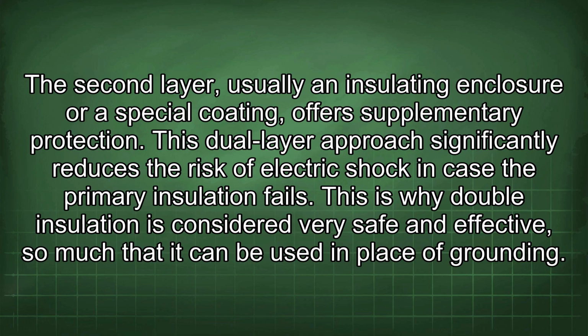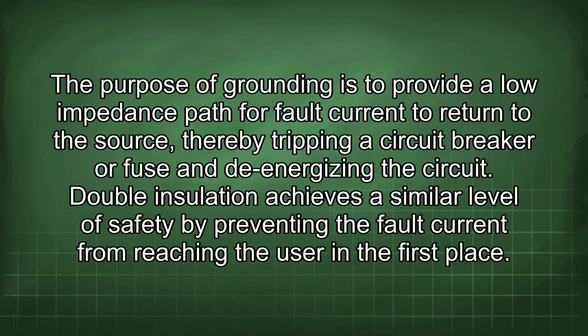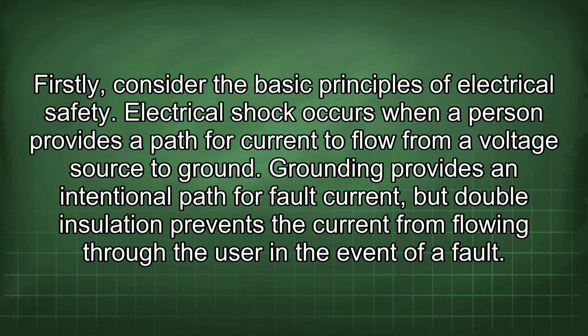This is why double insulation is considered very safe and effective, so much that it can be used in place of grounding. The purpose of grounding is to provide a low impedance path for fault current to return to the source, thereby tripping a circuit breaker or fuse and de-energizing the circuit. Double insulation achieves a similar level of safety by preventing the fault current from reaching the user in the first place. Firstly, consider the basic principles of electrical safety.